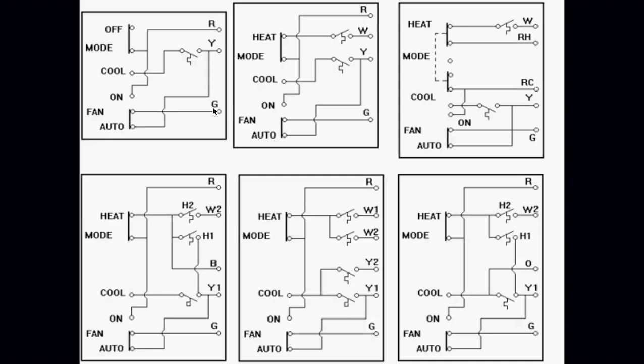Okay, this page is another one of these pages that I would probably recommend saving. The top left thermostat here, I'm basically saying it's number one. This is my basic cooling thermostat. It has an R, Y, and a G. R is my feed from my transformer. Y goes to my outside unit, and G goes to my fan relay. That is my basic cooling thermostat.